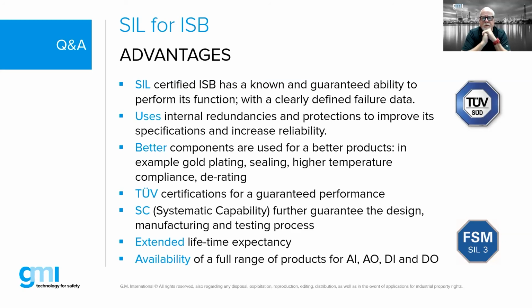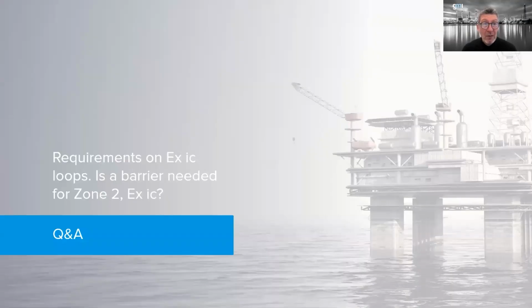In oil and gas today, most applications require some kind of SIL rating. So if you're in oil and gas and using IS, then a barrier is a mandatory requirement. That's why you find them all certified. We have SIL3 barriers as well as SIL2.